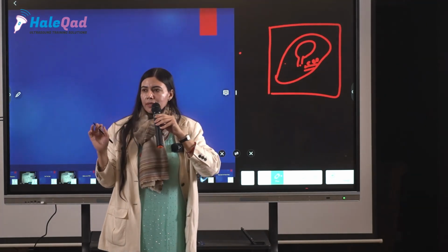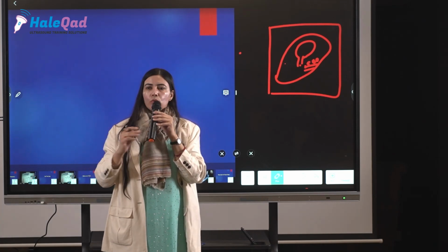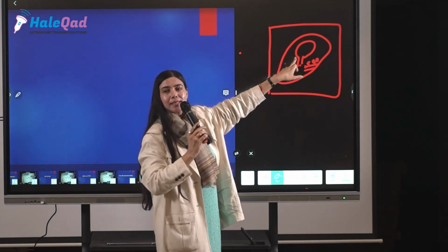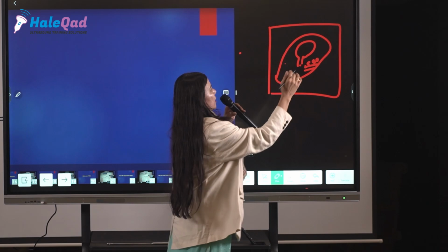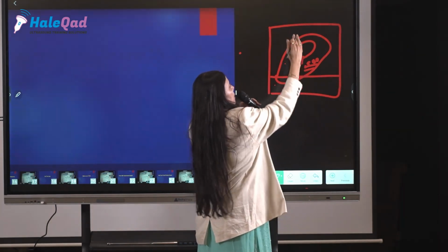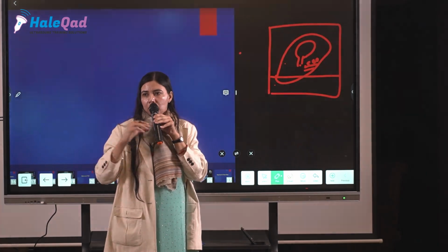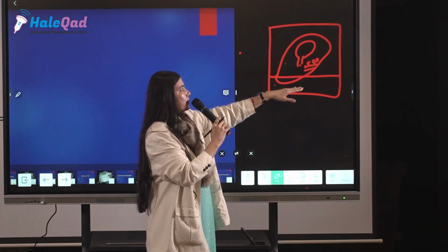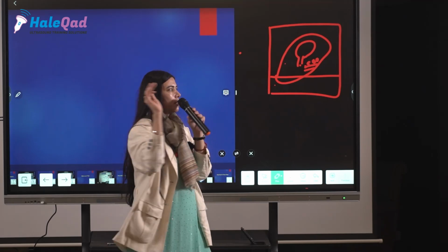I am not discouraging you from using the zoom button, but what I am telling you is, first decrease the depth, because you want to see this region. Decrease it, and your machine will show this only. Increase the frequency a bit, because increasing frequency will increase the resolution. Decrease the depth. Set your focal zone, most important.